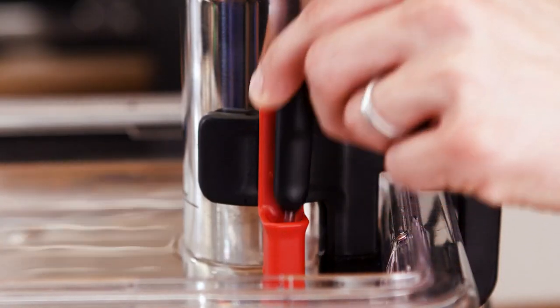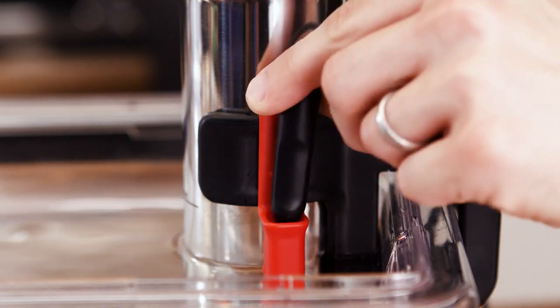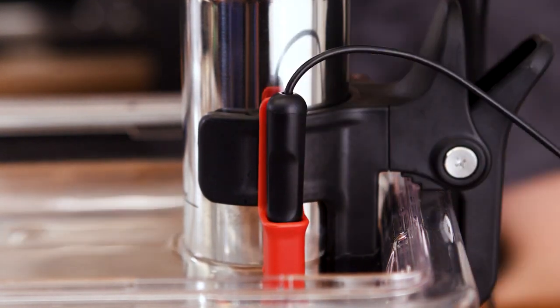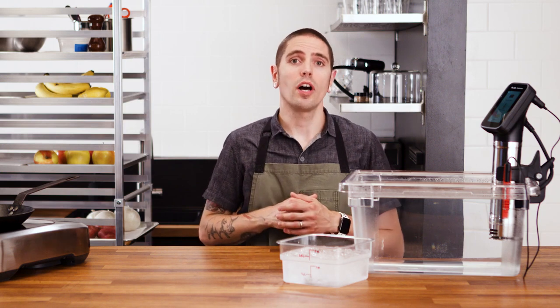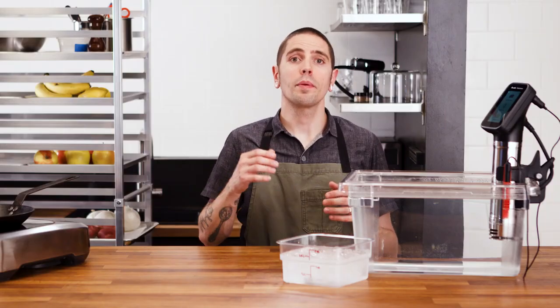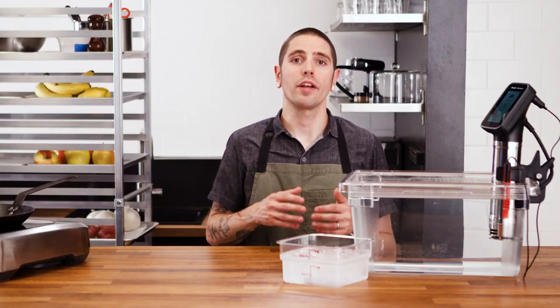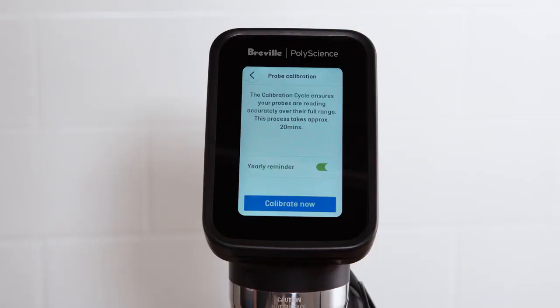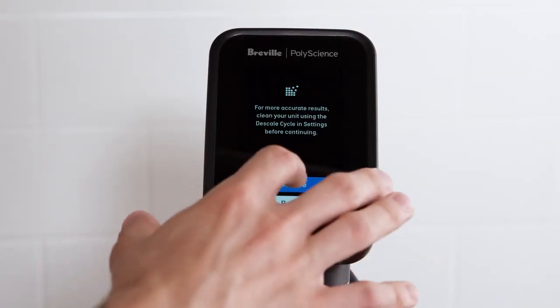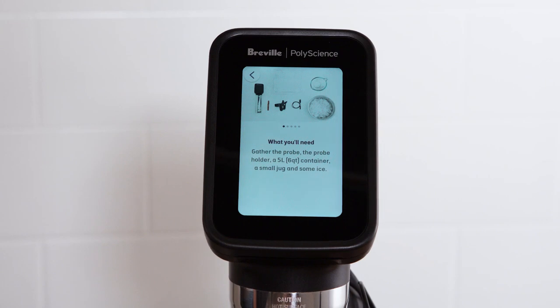To begin, ensure that your appliance is submerged to a level that will allow the probe tip to sit in the bath. You'll also need a small ice bath nearby. Connect the probe that you wish to calibrate and select Probe Calibration from the settings menu. You'll be prompted to turn a yearly calibration reminder on or off. When finished, select Calibrate Now and follow the on-screen prompts to calibrate your probe.